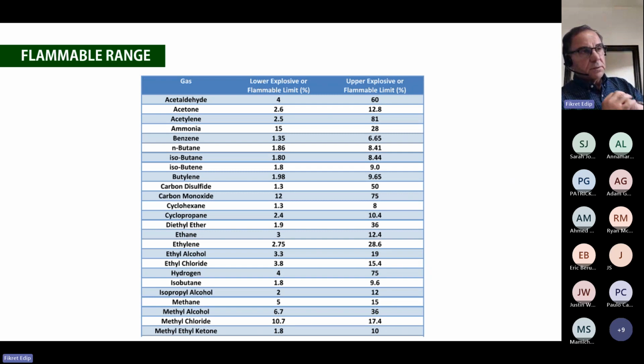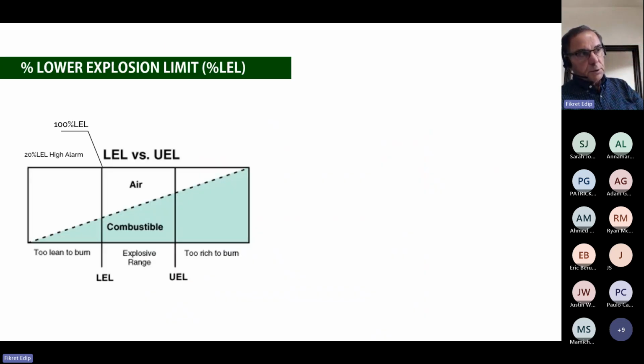And this is a list of some gases showing you their lower flammability level. For instance, if you look at benzene here, it's 1.35. What does that mean? It means that if it reaches 1.35 in an ambient, and there is a spark and oxygen, kaboom, there's a fire. So this is something you need to pay attention to. And I can show you this in a graph. If you look at the left side, as the gas starts leaking from the premises, when that leaked gas reaches 20% LEL, I'm going to give you a high alarm. We will never ever let it reach 100% LEL. When it reaches 100% LEL and there's oxygen and a spark, there is a fire. You cannot stop it. Therefore, we need to detect it before it reaches 100% LEL.